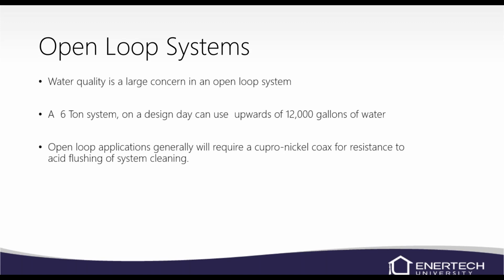Normally in open loop, we're going to put the cupronickel heat exchanger in there, and that's so we can clean it. We can use some acid-based cleaners to clean those deposits off, and that's why we use the cupronickel, is for the acid cleaning. It won't pit as bad. It's a little bit more robust. So you can use cupronickel heat exchanger on a closed loop. It's not going to hurt anything.